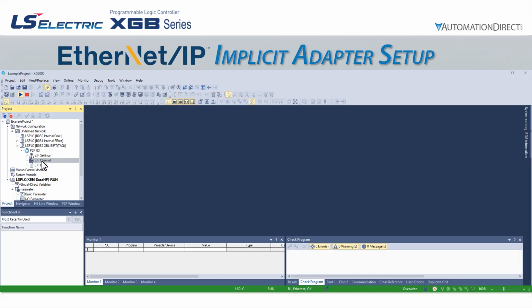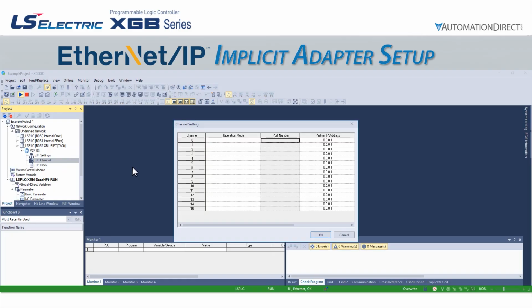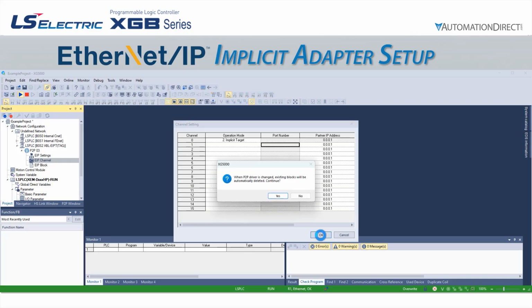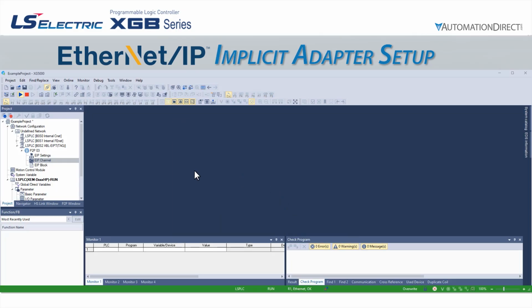This opens the channel setting pop-up window. We will use channel 0 and select implicit target for the operation mode. Implicit target for LS is the same as an implicit adapter. The port number and IP address sections are left alone. We can then click OK. We are now ready to create a tag that will be accessible by an implicit scanner.